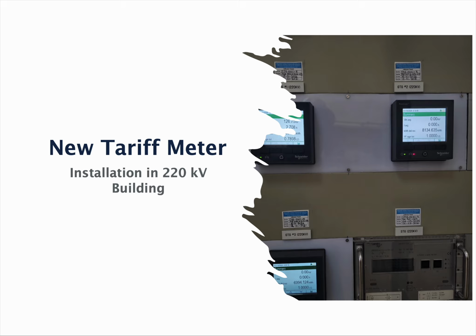Tariff meters. After the generator, the second most important part of the power station is the tariff metering system, because it converts produced energy into money, allowing the plant to invoice and get paid. If the produced energy is not measured correctly, it cannot be settled correctly. If it cannot be settled correctly, it cannot be invoiced. At that point, all effort invested in operating the plant does not result in revenue.